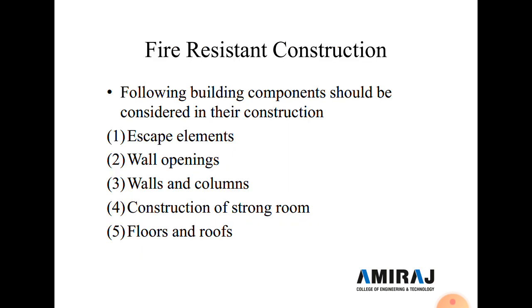Now next is fire resistance construction. Here the following building components should be considered in fire resistance construction. First is escape elements, second is wall openings, third is walls and columns, fourth is construction of a strong room, and fifth is floor and roof. Here we discuss them one by one. First we discuss escape elements. Escape elements like staircases, lobbies, passages or corridor entrances should be constructed from fire resistant material. So during a fire this type of structure is not damaged by the fire.